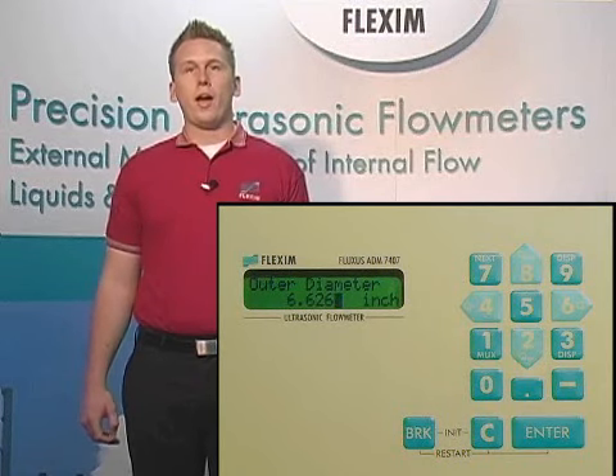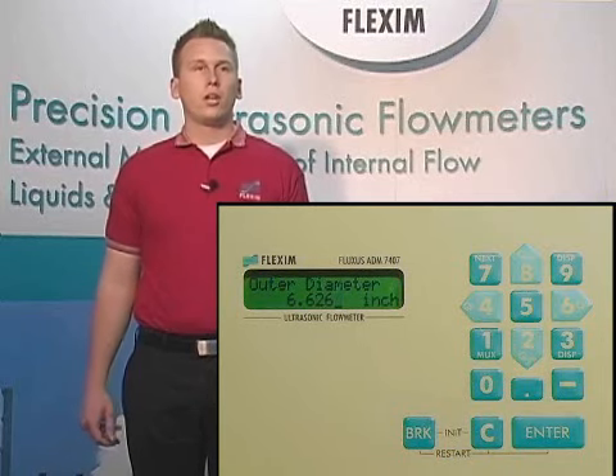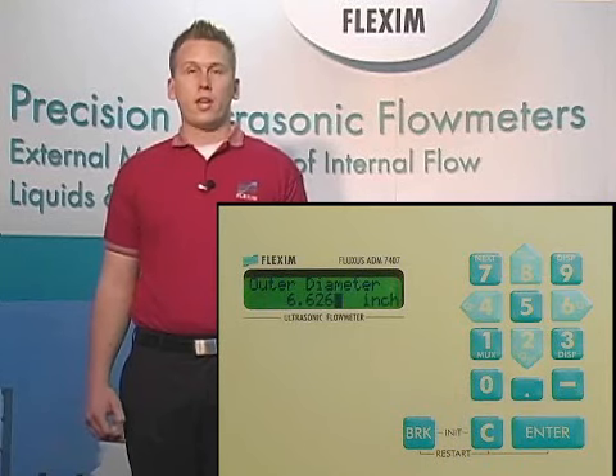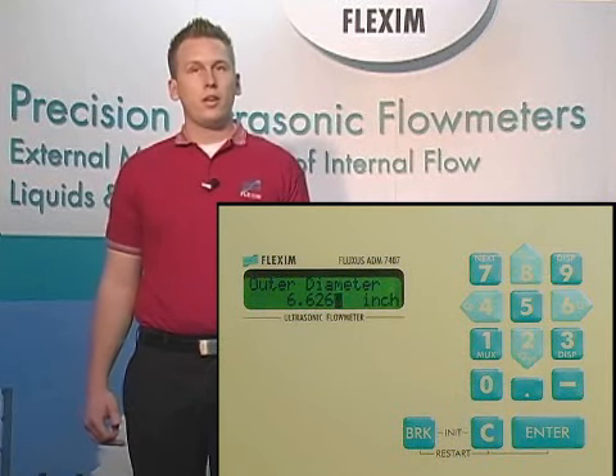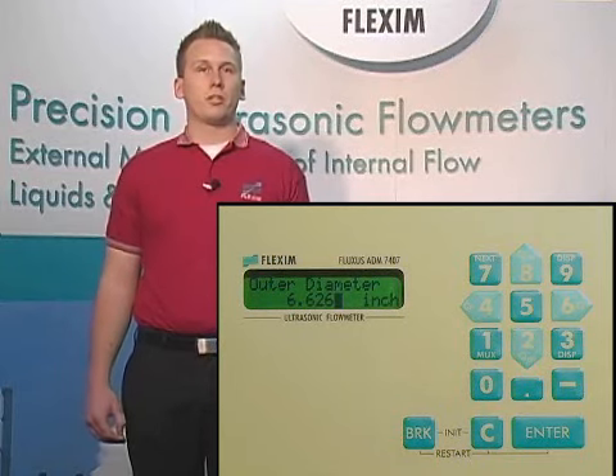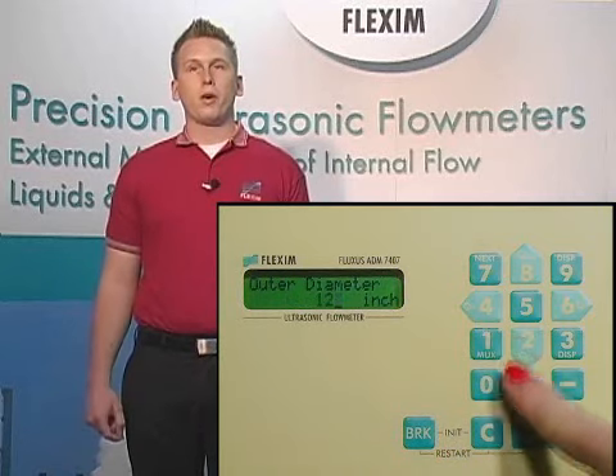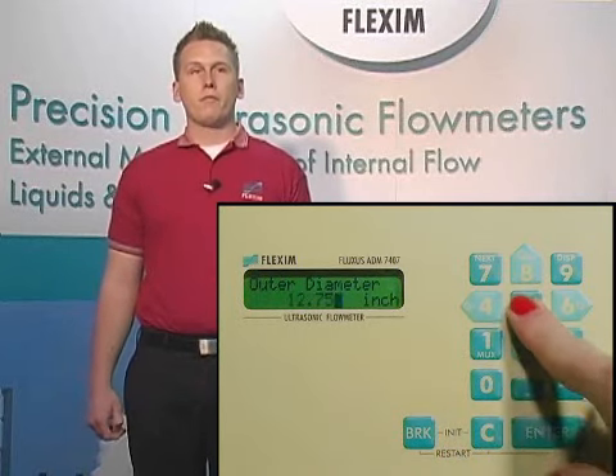If we're trying to measure on a 6-inch pipe, for example, our outer diameter is actually 6.625 inches, not 6 inches. On a 12-inch pipe, our outer diameter is actually 12.75 inches and not 12 inches. So the key here and everywhere in our menu system is to put in the actual dimensions and not the nominal ones. Let's enter the OD now for a 12-inch pipe, 12.75, and hit enter.